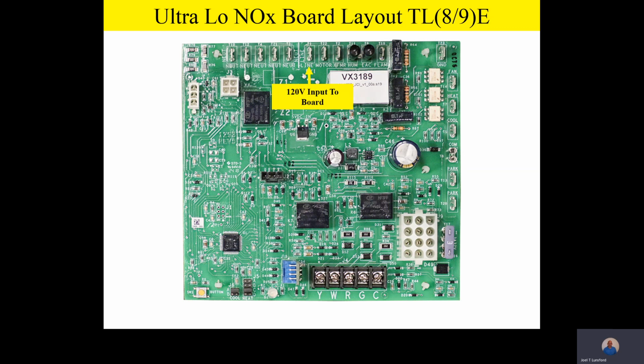So from our power source feeding the furnace, I believe it's a black wire, they'll plug right on to line, and that line is the 120 volt input to the board. Right next to that, we have our 120 volt output to our ECM motor. Now, team, remember something about ECM motors. The ECM motor is a high efficiency motor.